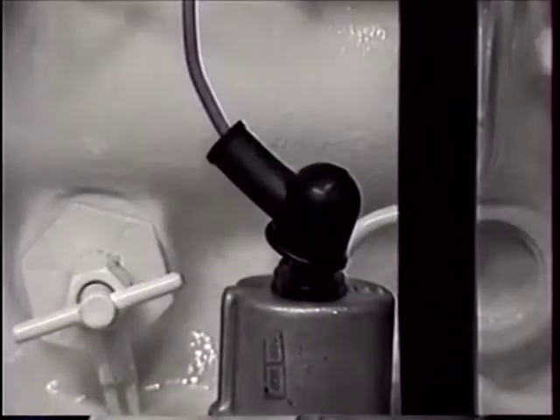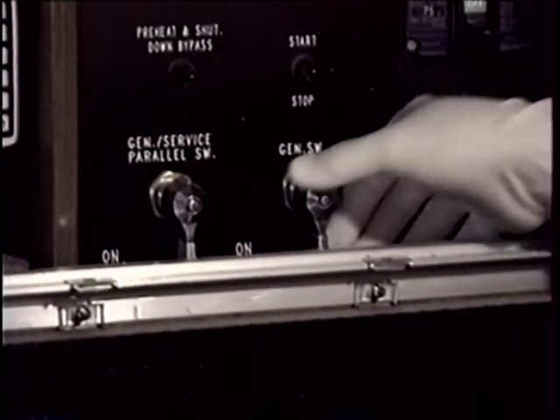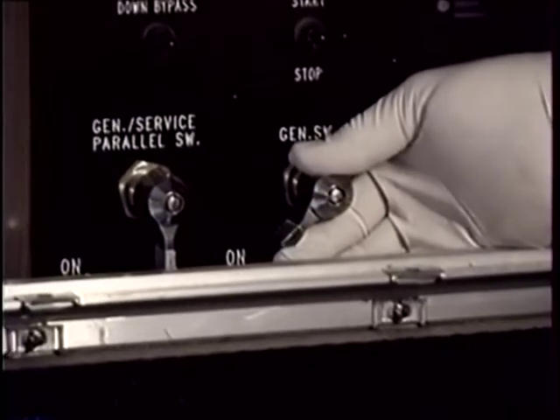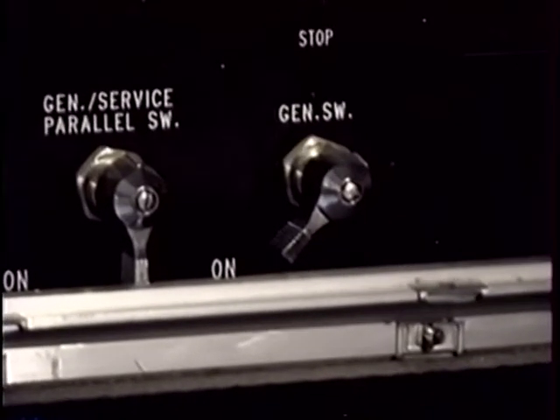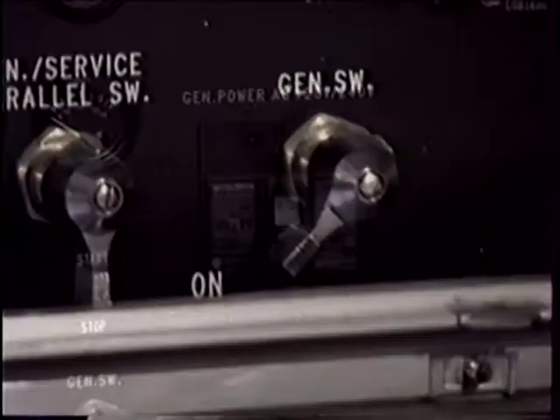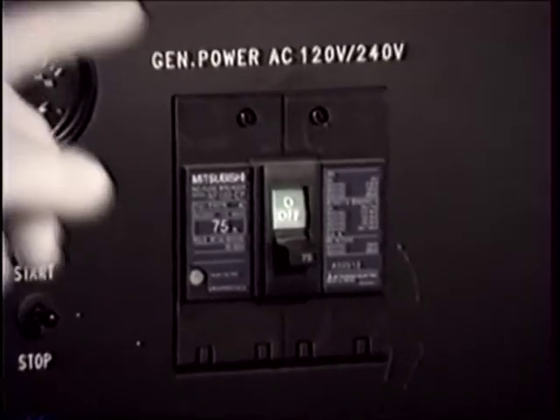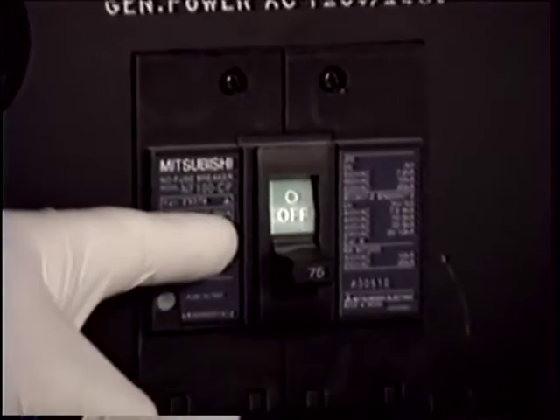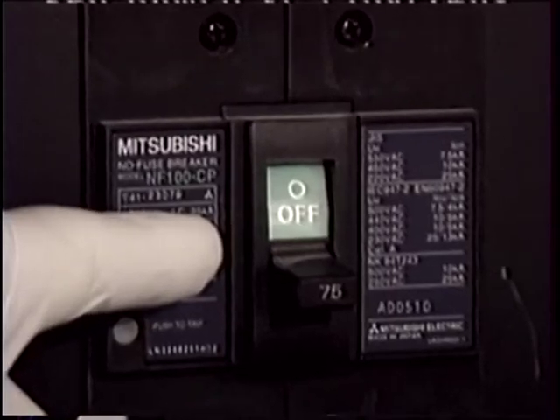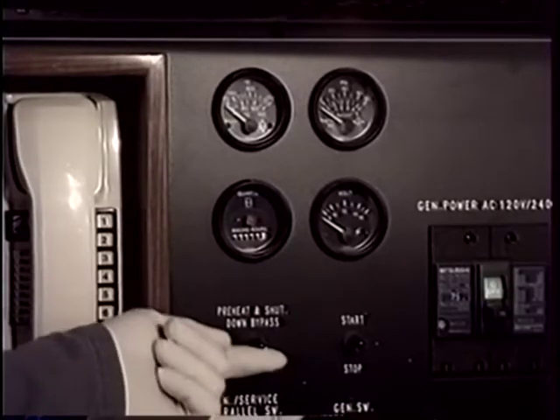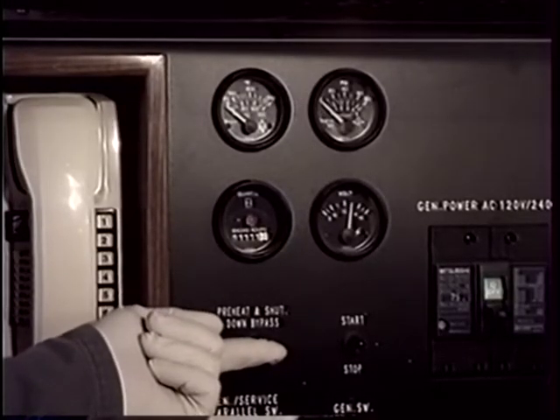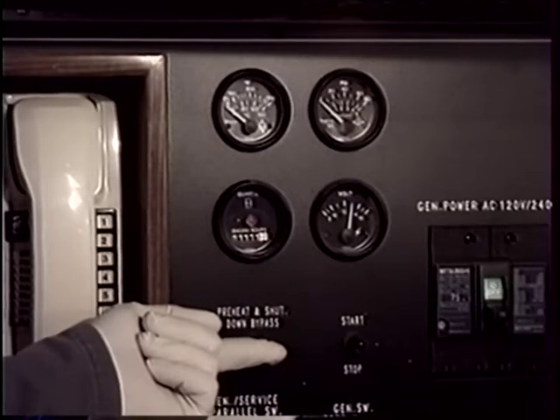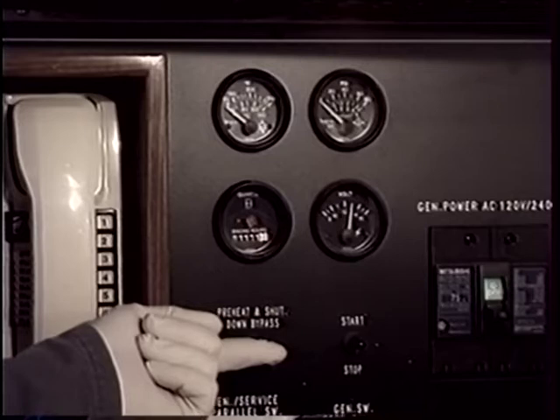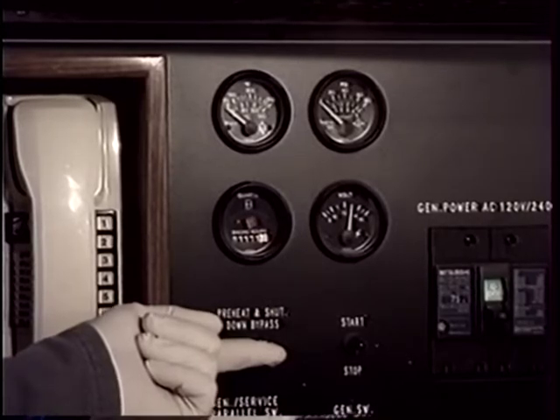With these preliminary checks having been done, you can now begin the start procedure. Turn the battery switch to the on position. Make sure that the load circuit breaker is open or load selector switch is turned off. Hold the preheat switch in for 10 to 15 seconds.